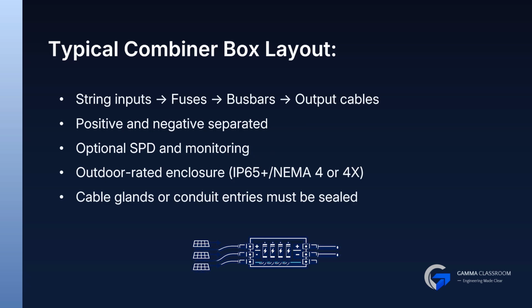Each string enters through a fuse, connects to a busbar, and exits through a single pair of outgoing cables. This layout ensures that if one string fails, the others keep operating safely.